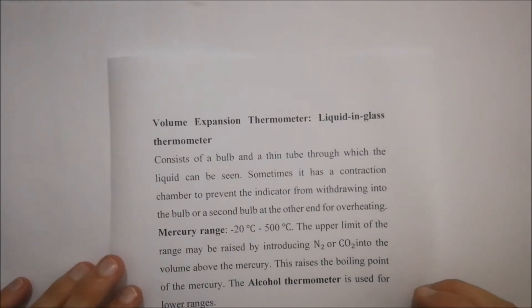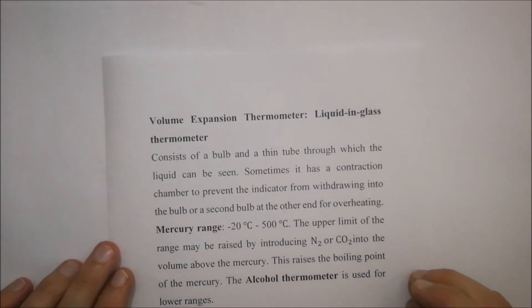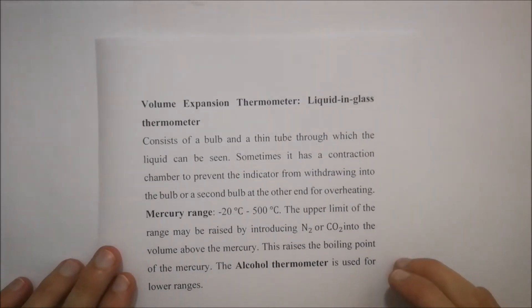Then we're going to be looking at volume expansion thermometer, liquid in glass thermometer. It consists of a bulb and a thin tube through which a liquid can be seen. Sometimes it has a contraction chamber to prevent the indicator from withdrawing into the bulb or a second bulb at the other end for overheating. Your mercury ranges from minus 20 degrees Celsius all the way up to 500 degrees Celsius.